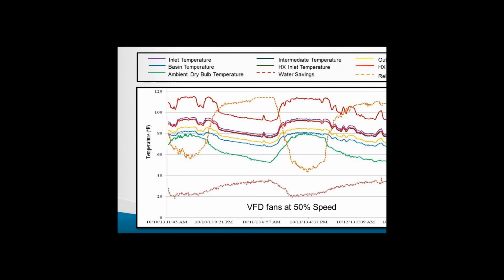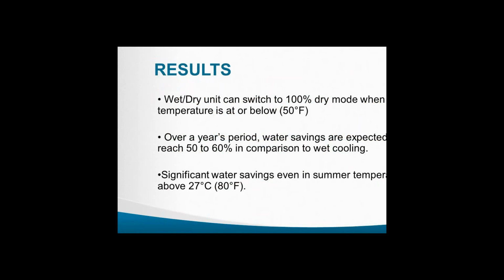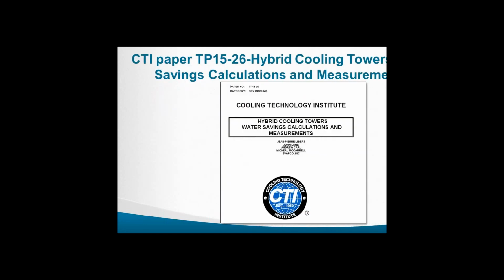And they saw that during the night is where they had the most water saving, which makes sense with everything down, wet bulb, dry bulb temperature. As a result, they're saving 50 to 60%, that much water saving, so it's in line with what you're getting from the supplier's computer programs and software. You can save water even in the summertime, and for the winter you can have a high switchover point around 50 degrees. So it's a good cooler to use for a lot of applications.